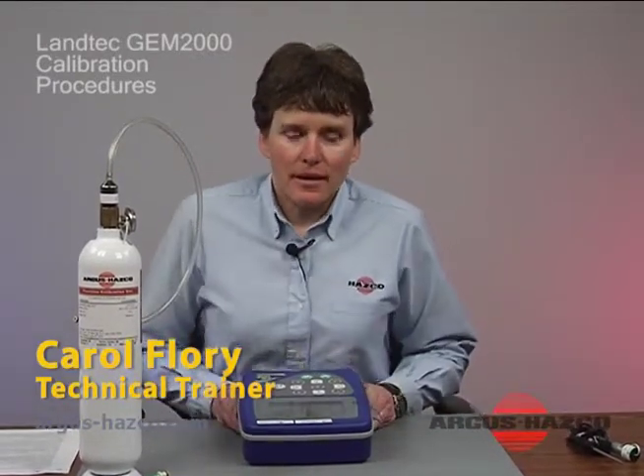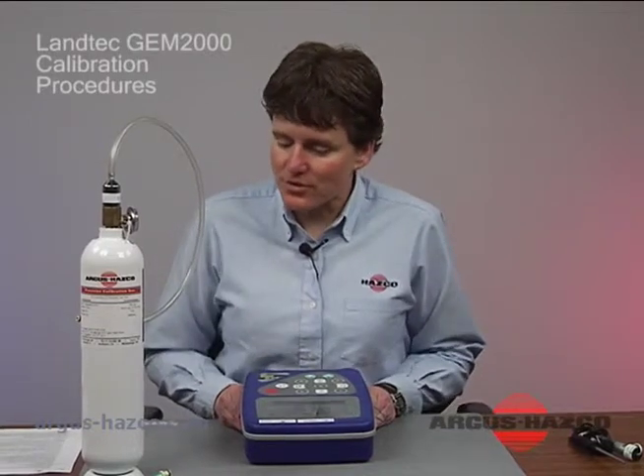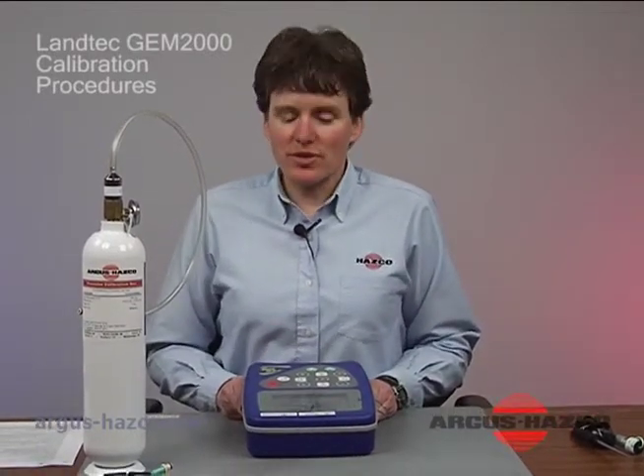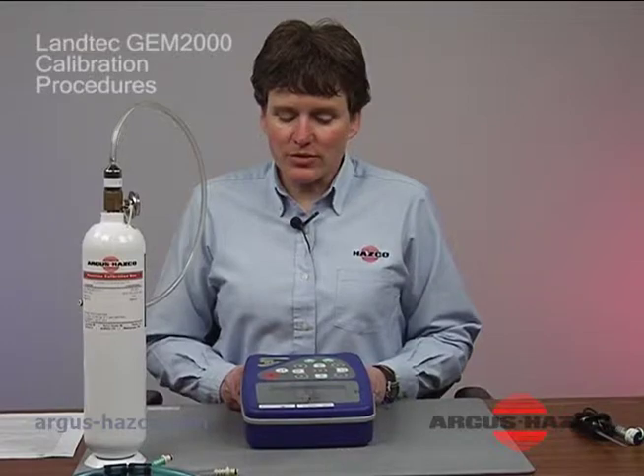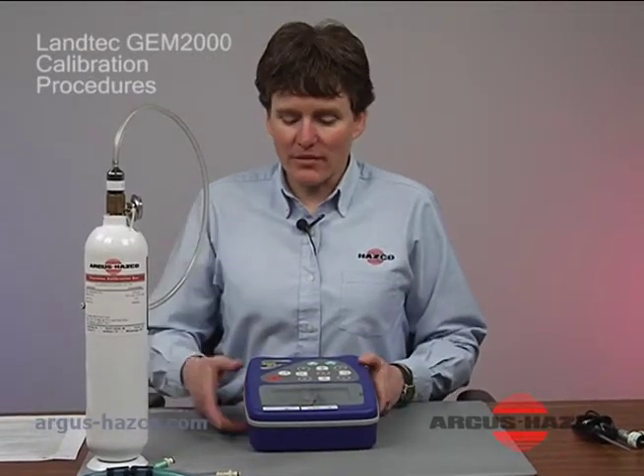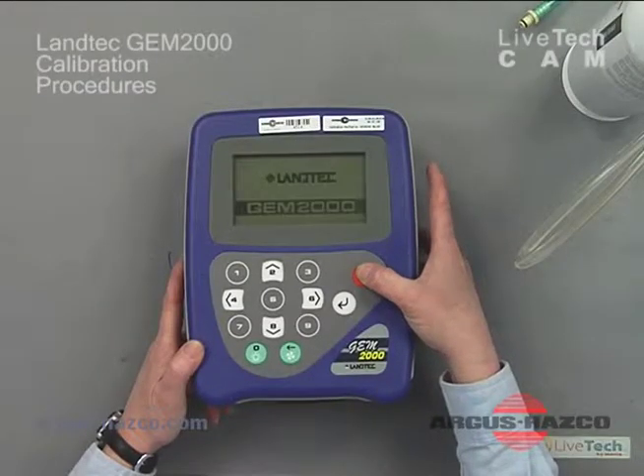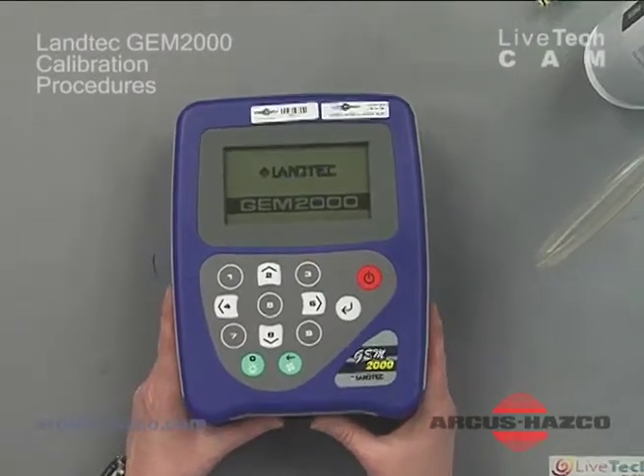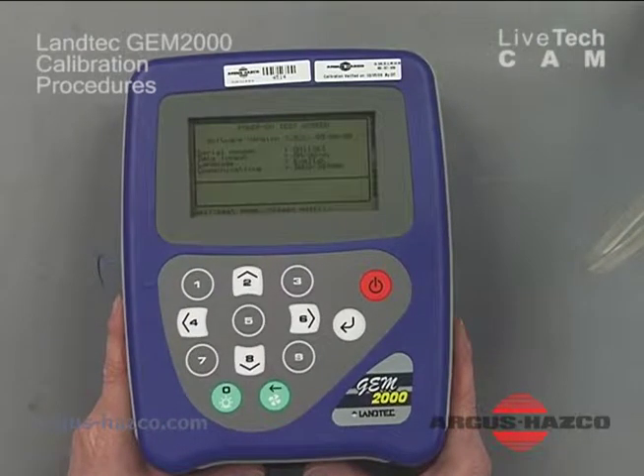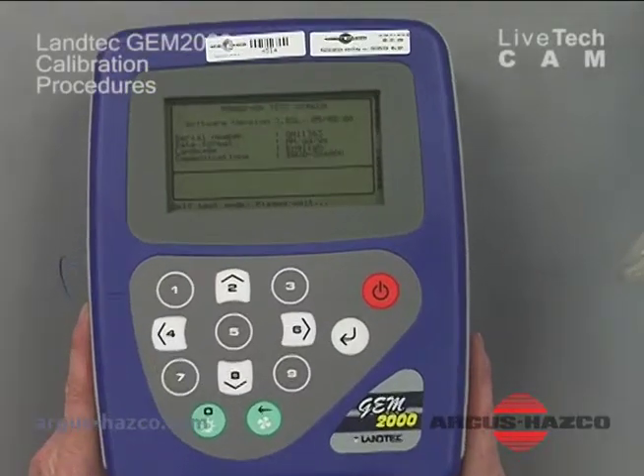The calibration of the GEM 2000. On the GEM 2000, you can perform field calibrations on the unit, and what we want to do is go ahead and power the unit on first. Hit your power key. Your display will come up, and it will give us a power on test screen.